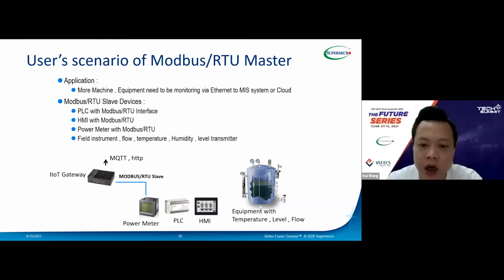Here is a solution for manufacturers with legacy equipment, for example an HMI, PLC, or power meter at the manufacturing floor right now. The problem is these are legacy systems that don't have the capability to link data to the cloud. So what we do is we don't have to change all that equipment to the latest version; we simply add on the gateway using Modbus RTU to hook up that data, remote config it, and send it through MQTT or HTTP to the IT infrastructure.